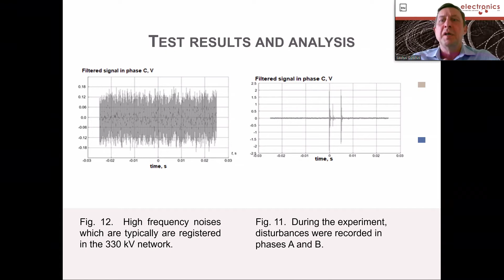When you measure using measurement transformers or other devices, they are not so precise, and it's not possible to measure corona discharge voltage, and it's not possible to decide whether corona occurs or not. You know that something is happening in the power line, you register it, you see that other voltages or a fault exist, and you know that corona should exist at the same time as this measurement.